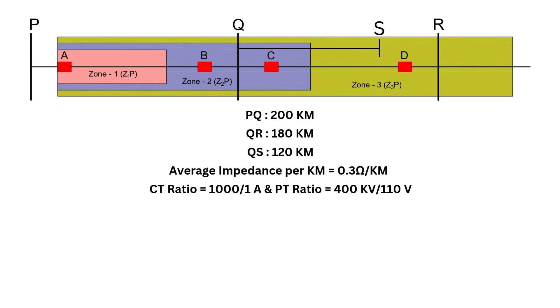Let's see how we calculate the impedance settings for each zone. First, we calculate the total line impedance for PQ, 200 × 0.3 = 60 ohms. Since zone 1 covers 80% of the line length, the impedance setting will be 0.8 × 60, which is 48 ohms.